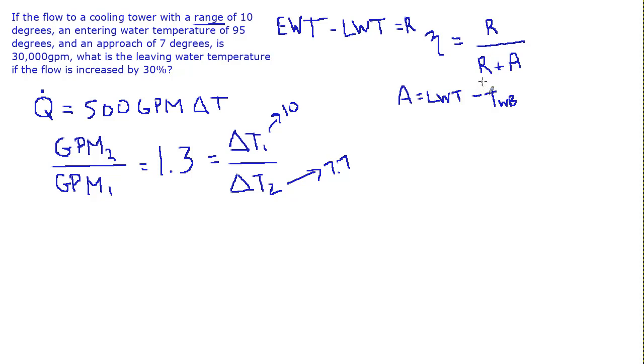And approach is leaving water temperature minus the wet bulb temperature outside. So when you put that all together, what is range plus approach? It's entering water temperature minus leaving water temperature, plus leaving water temperature minus wet bulb. So the leaving water temperature cancels out. You end up with just entering water temperature minus wet bulb temperature.